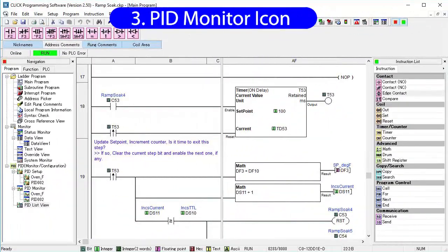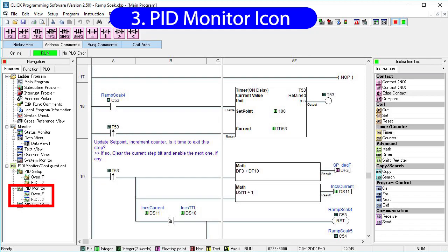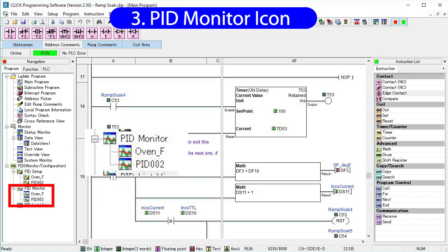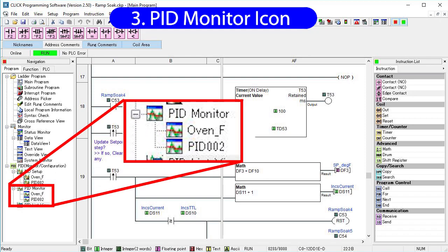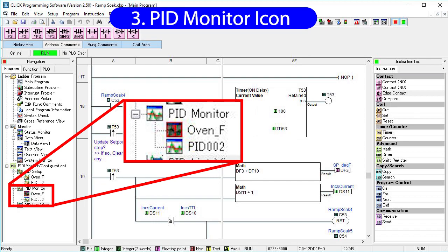You may have noticed as we went through our demos that the PID monitor icon changes. If it looks like this, then everything is great. If it has a red X through it, then it means you are not connected to the PLC, so you can't monitor anything. Finally, if you see a red exclamation point like this, it means there is an error in the PID loop.